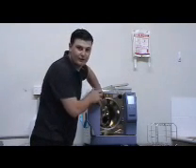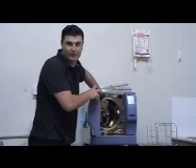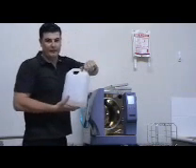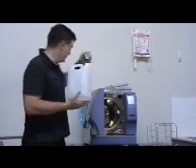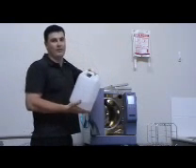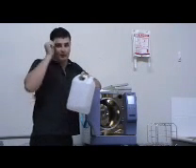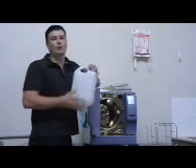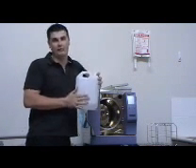So we have our drain tube blocking off the chamber and we have our funnel set in the spout. With distilled water — it is important to mention now — we do always recommend distilled water rather than demineralised. Over the life of your steriliser, you will get optimal performance out of distilled water.